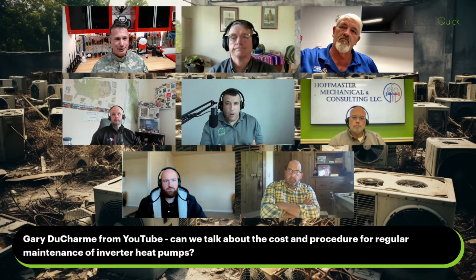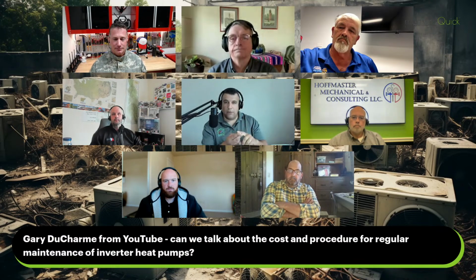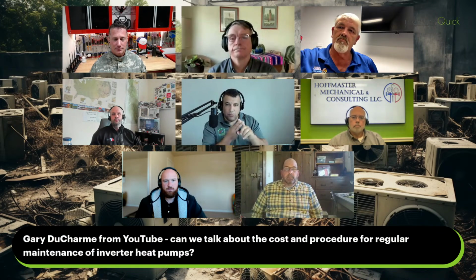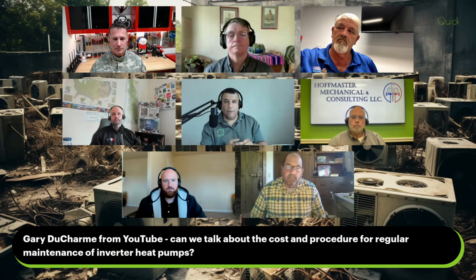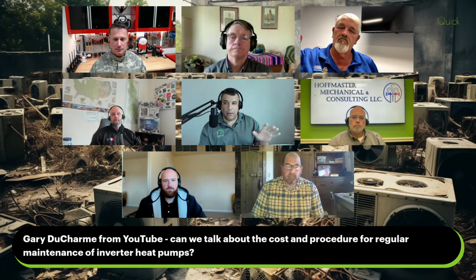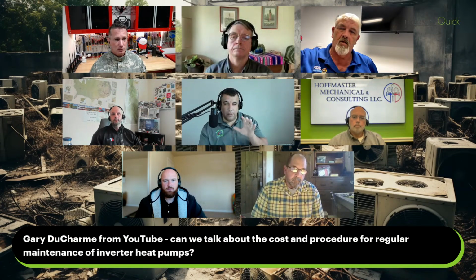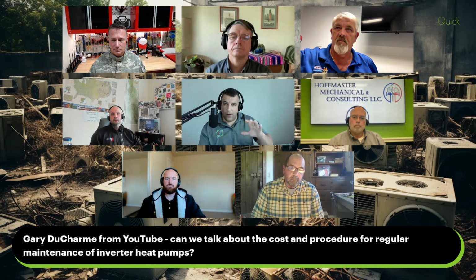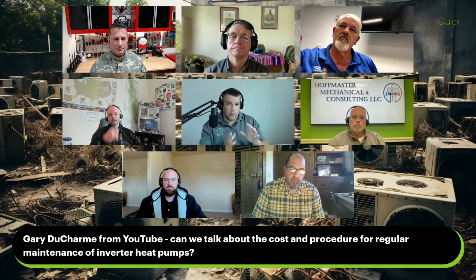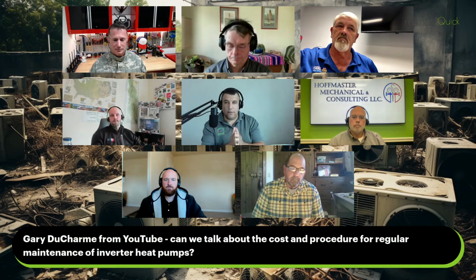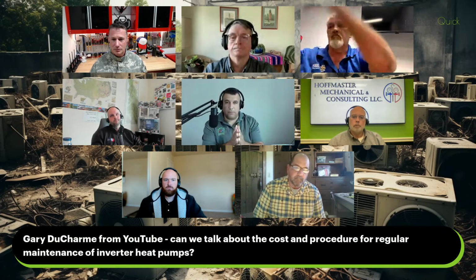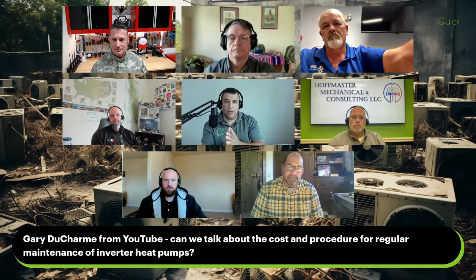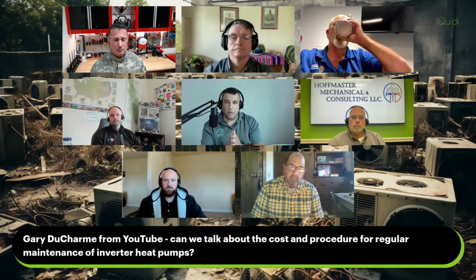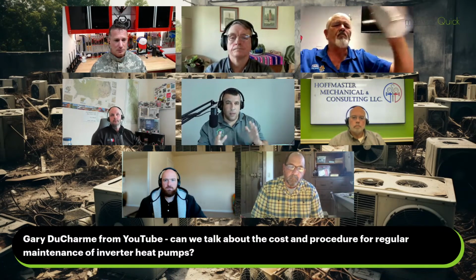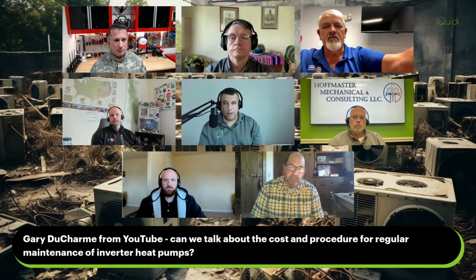The only reason we come back for maintenance is cleaning and maybe tightening electrical connections. There's huge value in maintenance, but twice-a-year isn't necessary if we do one really good visit and use it as an opportunity to connect with customers. Twice-a-year maintenance was more for companies wanting to get in front of customers twice a year, maybe to sell something they need—or don't need. But for a typical residential system, if you do a good job, once a year should be plenty.